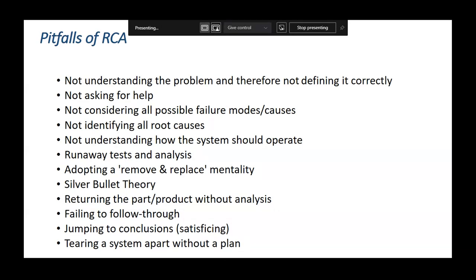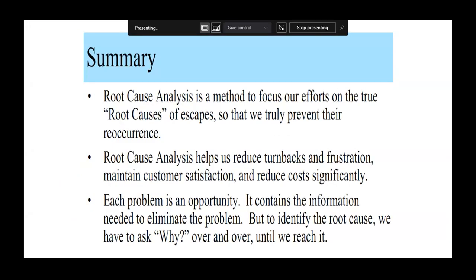When checked, the bilirubin was continuously out but all other parameters were fine — suggesting the problem was with bilirubin specifically, not the machine. The root cause was that the bilirubin calibrator had been kept outside the recommended storage conditions, causing it to deteriorate; the calibration deteriorated accordingly, producing a systematic error. This demonstrates that a 'remove or replace' mentality and 'silver bullet theory' are dangerous. You must disintegrate the problem and check all areas — like HPLC where the column was being repeatedly replaced when the real problem was the buffer or the pump. Failing to follow through, jumping to conclusions, or tearing a system apart without a plan are all pitfalls of RCA.